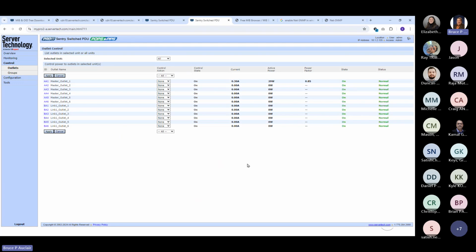Energy is an option for kilowatt hours. That's not something you're going to be constantly polling, but it is an option that you could use for billing purposes. For example, you take one measurement at the beginning of the month or the beginning of a week, whatever period you want to bill by. Take one reading at the beginning, take one reading at the end, and then the delta between the two gives you a value that is the power consumed over that amount of time.